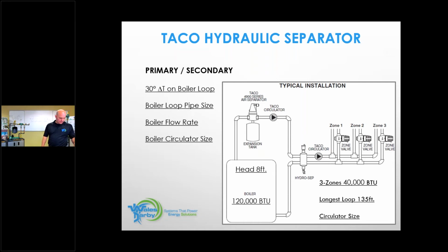One gentleman went with a 0012. Yeah, that's a big boy. You're paying up for that. We have another gentleman, one of our friends, with a 0026E. A 0026E will also work there, yes. That would work. But a 007 will do it too. 7's close. 7, 15, E3. They'll all work for that boiler side.